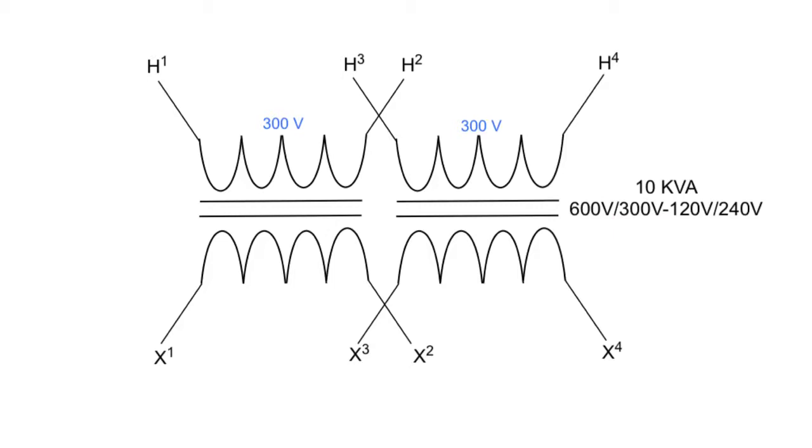Let's look at the X side, or the low side. We have the same situation. We have 120, 240 volts. We're going to take the lower of the two voltages, 120 volts, and apply that to each winding. Now we've determined what each winding is rated to handle.